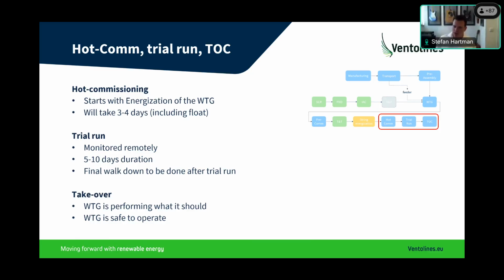So having energized the string, the hot commissioning starts. There are some final tests to demonstrate that the turbine is safe, and then the turbine is put into a trial run. Trial run takes 5 to 10 days, but I've seen them as short as 3 days. Trial runs are typically monitored remotely via the SCADA system.